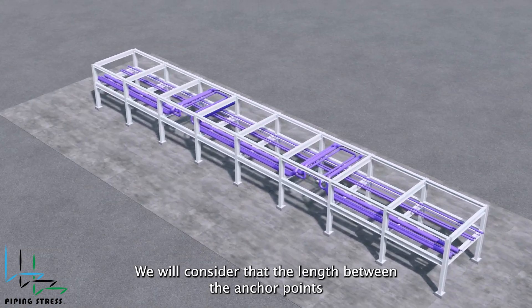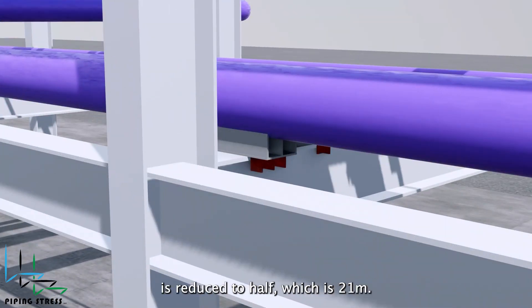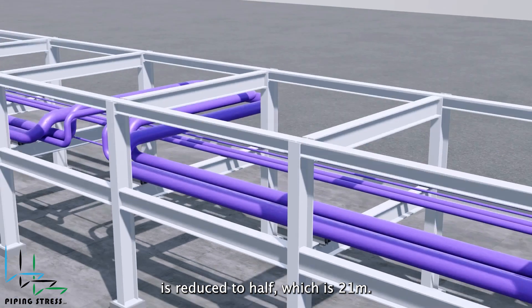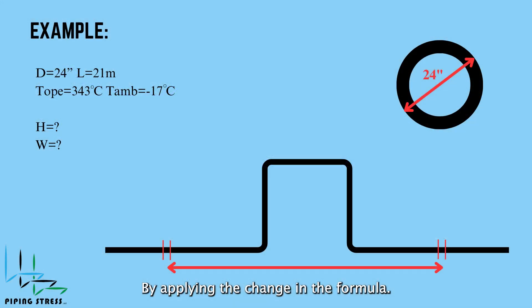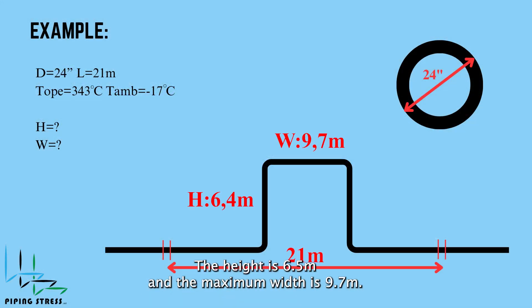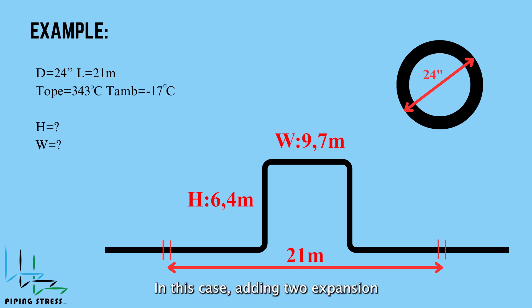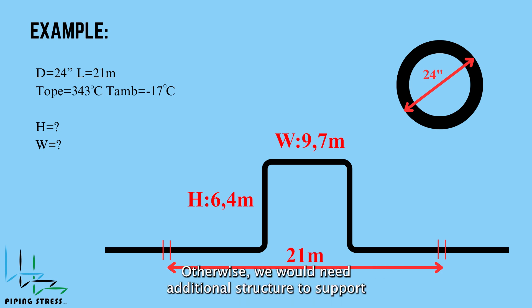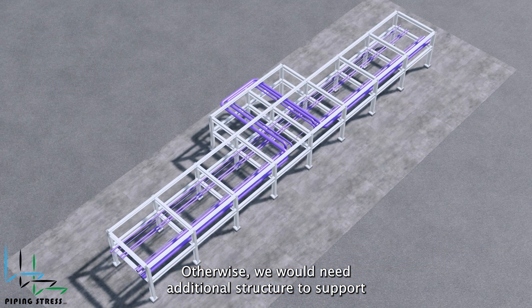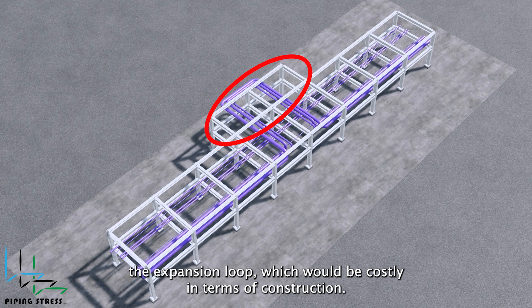We will consider that the length between the anchor points is reduced to half, which is 21 meters. By applying this change in the formula, the height is 6.4 meters and the maximum width is 9.7 meters. In this case, adding two expansion loops will suffice for a 6-meter wide pipe rack. Otherwise, we would need additional structure to support the expansion loop, which would be costly in terms of construction.